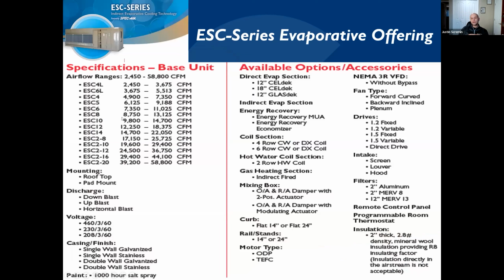So we can get into much more custom offerings with this type of equipment. One thing we can do is energy recovery, where instead of a single pass on the ESC series, we have a return air system that loops it back through, letting us continue to cool that air at a much lower operating cost.